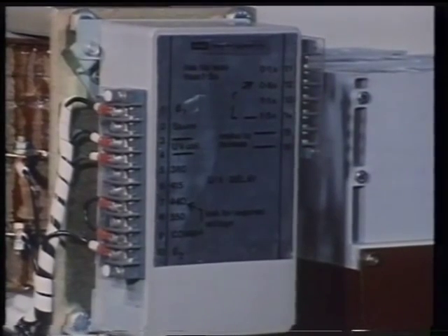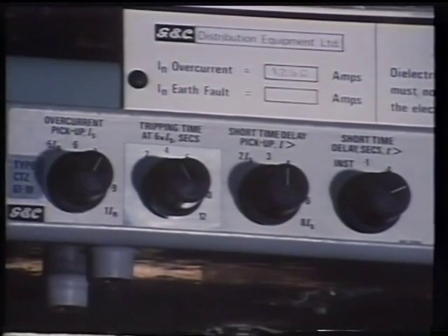Other protective devices for the AC generator are housed in the circuit breaker. They are under-voltage and overcurrent relays and short-circuit trips. They disconnect the AC generator from the bus bars if either a severe and prolonged voltage drop occurs, or the AC generator is overloaded, or a severe short circuit occurs on the system. Now we shall see some typical tests.